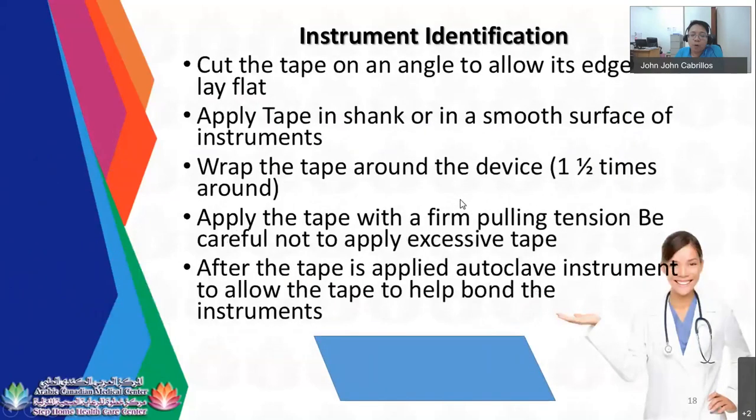So if you are putting an identification tape or autoclavable tape on your instruments, you need to cut the tape on an angle to allow its edge to lay flat. So as you can see on the lower part, that's the angle when you are cutting your tape, not a straight line. So apply tape in a smooth surface of instruments. You cannot apply any tape where there is serration, okay?